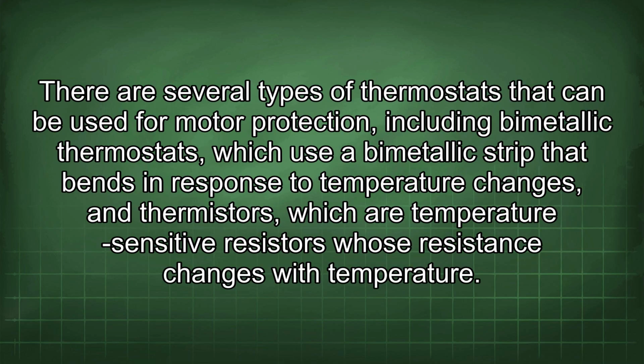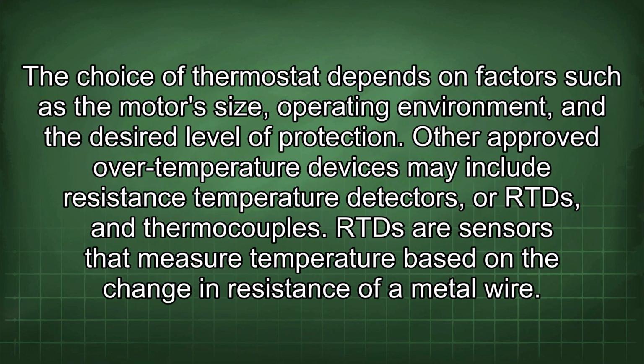There are several types of thermostats that can be used for motor protection, including bimetallic thermostats, which use a bimetallic strip that bends in response to temperature changes, and thermistors, which are temperature-sensitive resistors whose resistance changes with temperature. The choice of thermostat depends on factors such as the motor's size, operating environment, and the desired level of protection.